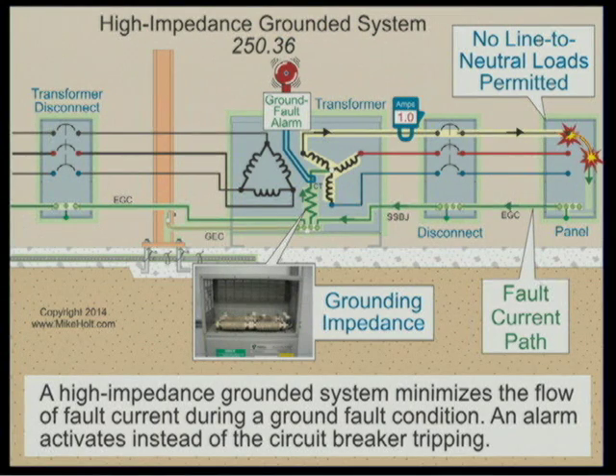Ready for this? Now, this is a 480 volt phase-to-phase application that when you have one phase go to ground, look at the fault current. 1 amp maybe, 3 amps, 7 amps, possibly as high as 10 amps. Guess what we don't have? We don't have the danger of an arc flash blast hazard. Now, you would have it if one phase goes to ground and then nothing is fixed. The alarm goes off. Nobody fixes that single phase ground, and then you have a second phase that goes to ground. Now you have a phase-to-phase 480 volt fault, which is devastating.